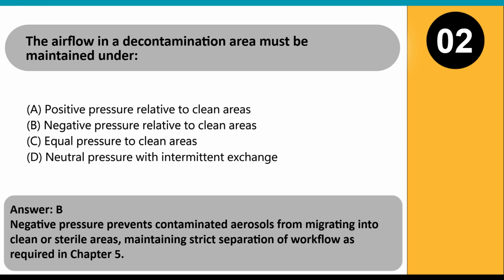Answer: B. Negative pressure prevents contaminated aerosols from migrating into clean or sterile areas, maintaining strict separation of workflow as required in Chapter 5.